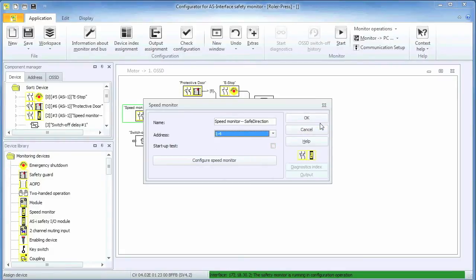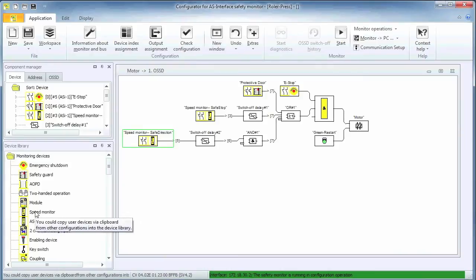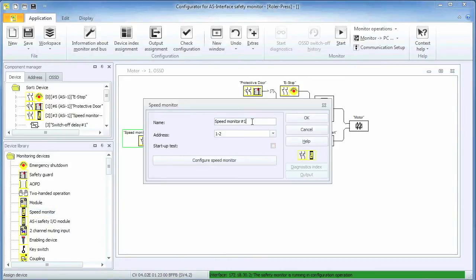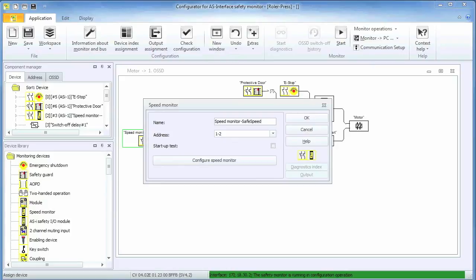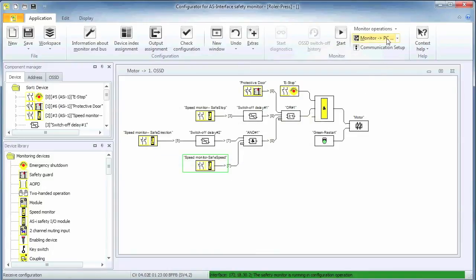Now we have to deal with an over speed situation. By dropping another speed monitor function block here, this one verifying that the speed of rotation is below the limit speed or critical rate, we assure that the motor is only powered as long as the press is spinning at less than the critical rate. The AND function enforces that both conditions are met, spinning in the proper direction and at less than the critical rate. The safe over speed signal is received via address 2.